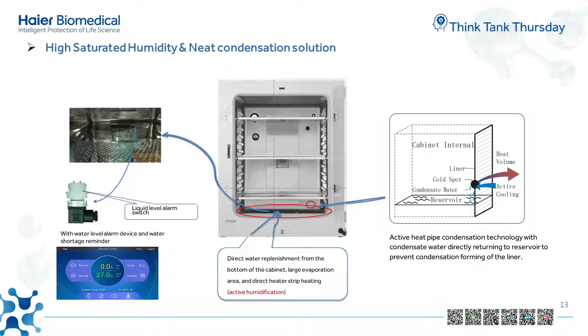And from the design perspective, there is a cold spot area in the rear of the chamber. The active cooling design is to reach the optimal humidity level to prevent the cells from drying out while keeping the condensation directly returning to the reservoir. So it's a neater solution while keeping high humidity for the culture and incubation research.